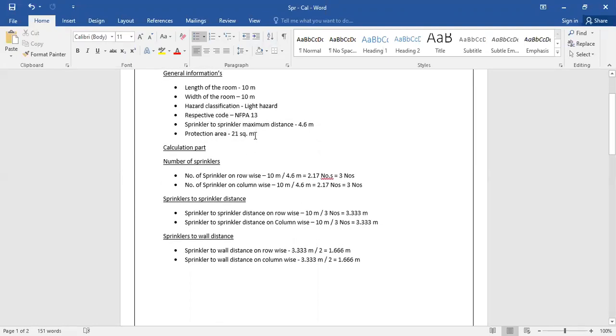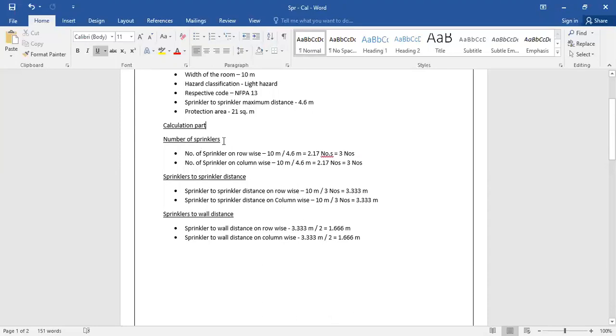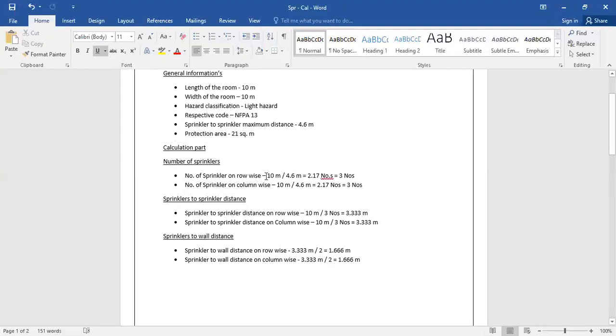After the general information, we move to the calculation part. The first part is the number of sprinklers, which contains two steps: number of sprinklers row-wise and number of sprinklers column-wise. For row-wise, we take the length of the room divided by 4.6 meters — the sprinkler-to-sprinkler maximum distance from NFPA 13 — and we get 2.17. We round up, so it is 3 sprinklers row-wise.